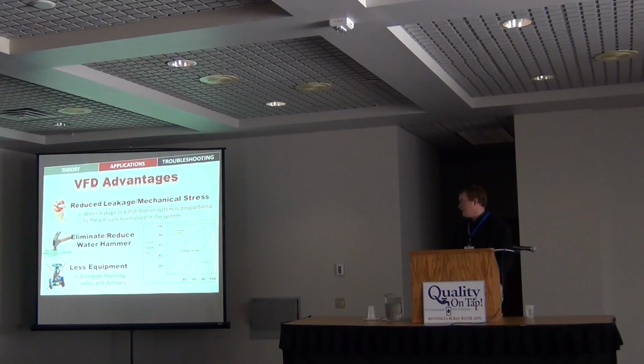Some advantages. Using a VFD reduces mechanical stress, and water leakage in the distribution system is proportional to the pressure maintained on the system. So if we don't need to maintain a really high pressure all the time, we can reduce that pressure, hopefully reducing leaks, reducing stress. If we reduce the stress on anything, it should increase equipment life. We're going to eliminate or reduce water hammer, which we don't like. Using a VFD to do that by ramping up slowly is a perfect application for that, especially on a big pump.